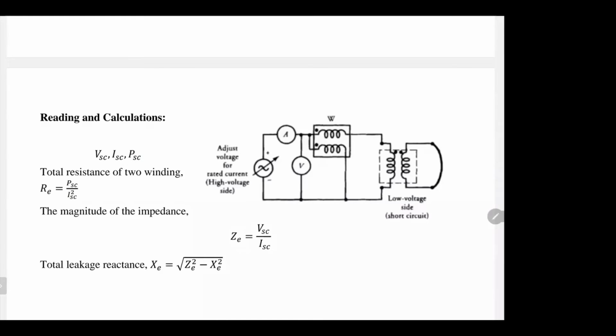But this test is really important because it can cause harm to the transformer if it's not performed right, so I want to mention it here. Open circuit is safe because there is no load, and the no load current is really small. But this one, you're going to short circuit. It means that the resistance is equal to 0. The current will be maximum.